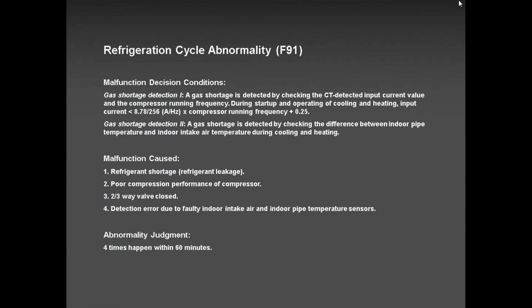Now, when you saw before, we were in the H error codes, and now we are in the F error codes. F error codes in most cases are not good because it's either the outdoor unit compressor or the outdoor unit PCB. So if it's the outdoor unit PCB, then that's good. You can always change the whole entire PCB and you're up and running.